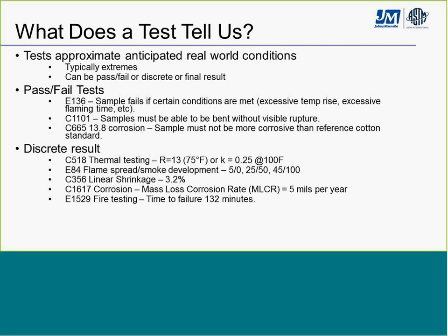Many people have heard about E84 flame spread and smoke development. We test the product and get a result, but usually there's some other judgment — it could be a building code, a government body, or an end user that has determined what's acceptable. Generally, if a product has a flame spread of 25 and smoke development of 50 or less, it can be left exposed. If the values are larger, you'd generally have to cover it up — but again, it depends on who is interpreting that. The C1617 corrosion test also gives us a number, and it's really up to a standard or specification to tell you whether that number is good or bad.